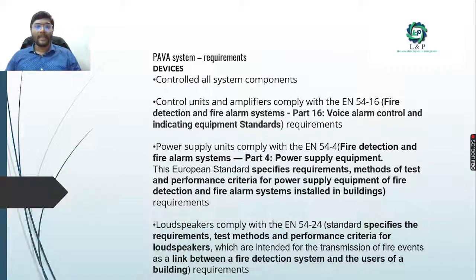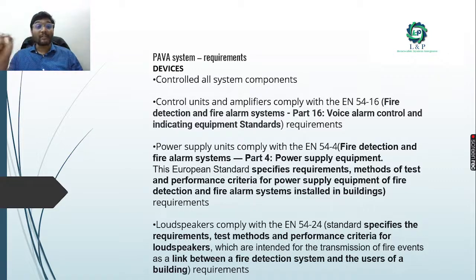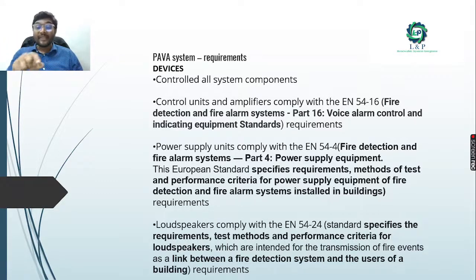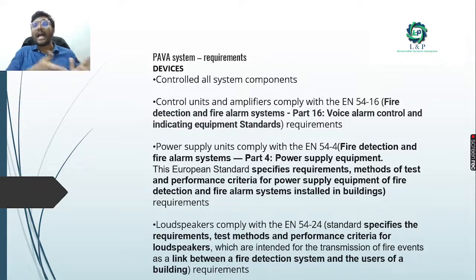Different speaker lines are needed in fire zones and loudspeaker zones. All system components should comply with relevant standards. The control units and amplifiers should comply with EN54-16 - Fire Detection and Fire Alarm Systems Part 16: Voice Alarm Control and Indicating Equipment. Power supply units should comply with EN54-4 - Fire Detection and Fire Alarm System Power Supply Equipment. Loudspeakers should comply with EN54-24, specifying requirements, test methods, and performance criteria.